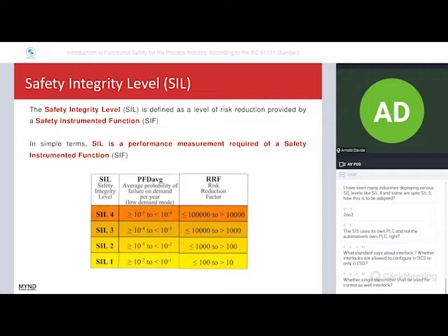The help from the standard 61508, that is the first standard for functional safety, is what is called safety integrity level, SIL. It is defined as a level of risk reduction provided by the safety instrumented function. By the safety instrumented function, not by devices. In simple terms, safety integrity level is the performance measurement required of a safety instrumented function. Checking the table from the 61508, we can see that we have 4 different levels of SIL, from the lowest to the highest, from SIL 1 to SIL 4.